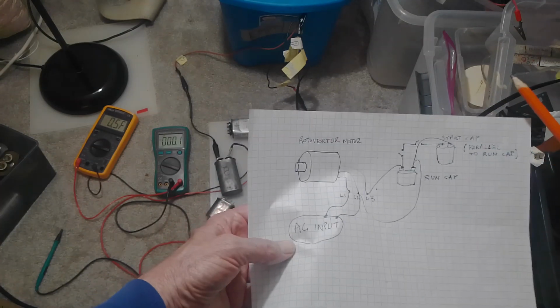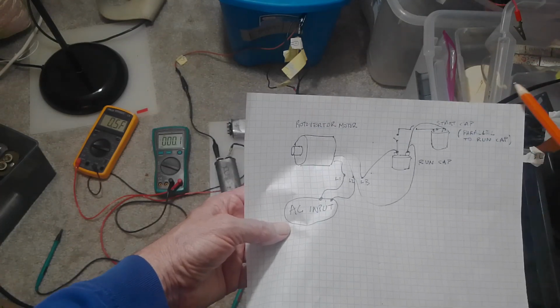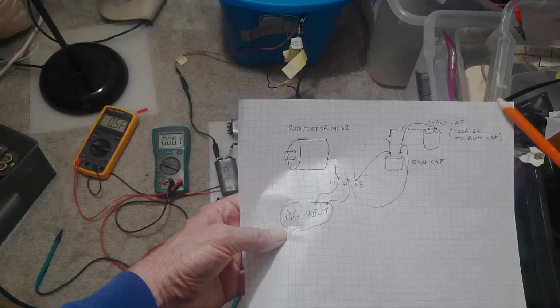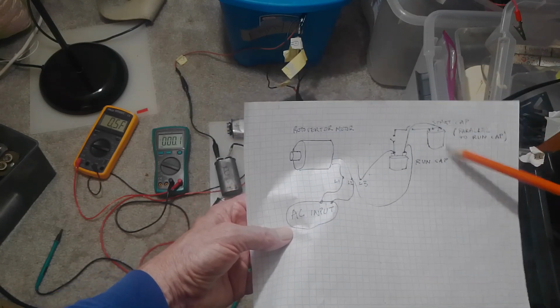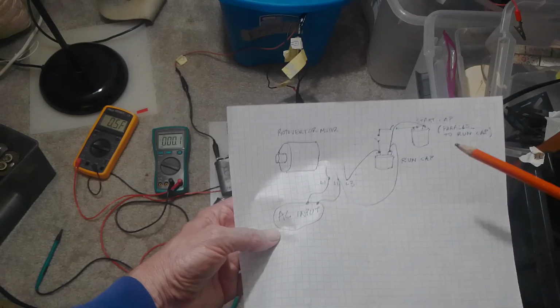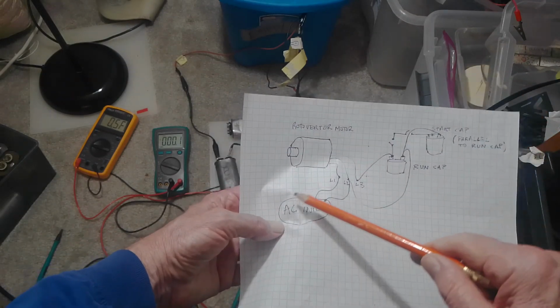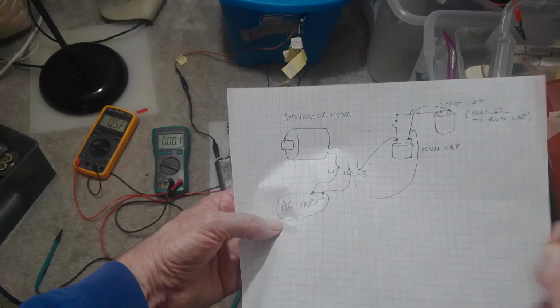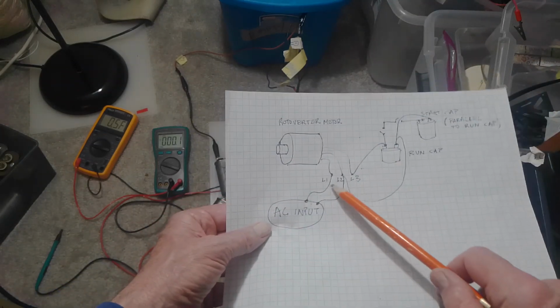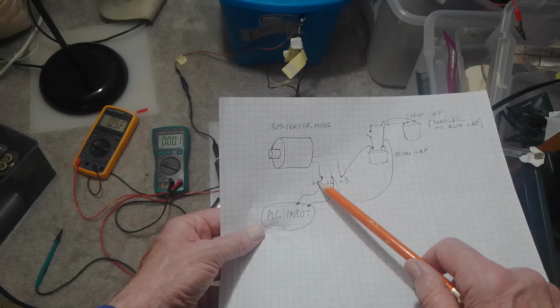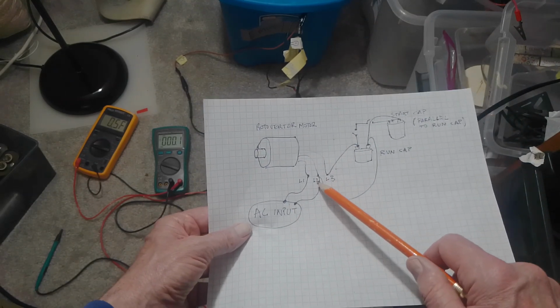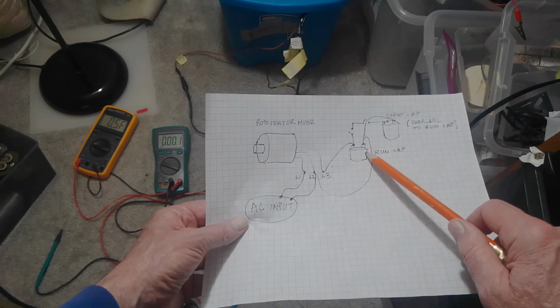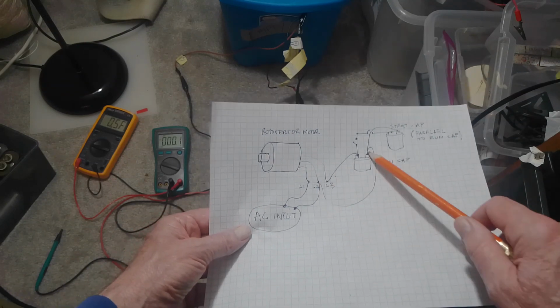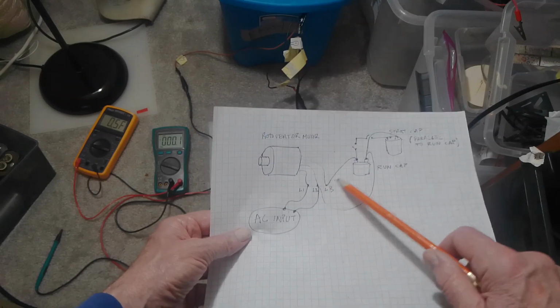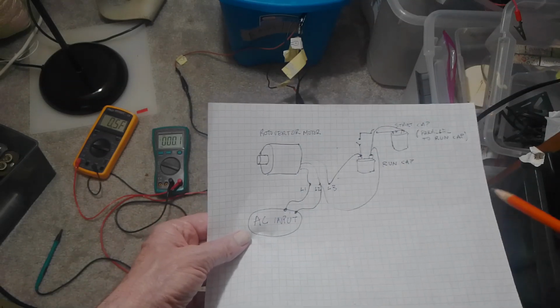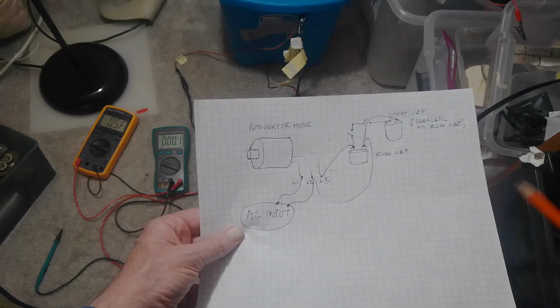So this is a 4-pole AC induction motor, 3-phase, and it's going 1800 RPM now. It's latched right in with the 60 hertz sine wave. And again, here's how you hook it up. You have your AC input. One side goes to L1 and the other side goes to L2. L2 shares a connection to one side of the run cap, and L3 goes to the other side of the run cap.